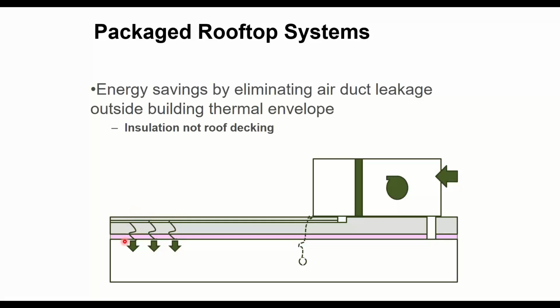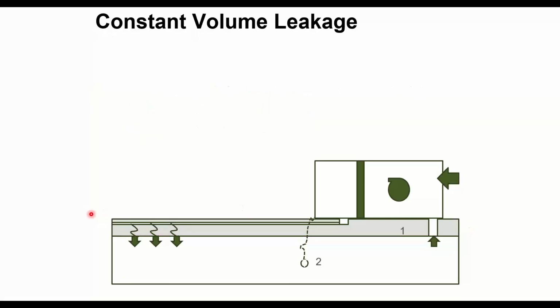But in regards to the air leakage, see if the little arrows pop up for me, right? All the air that's leaking out of my ducts in the ceiling cavity is actually leaking out of the building in most cases. If I have ductwork in the space and it leaks, it's like, oh, okay, you got leaky ductwork in your space. At least it still gets to the space. But when it leaks in ceiling cavities, walls, shafts, some of that might go back to the space. Some of it goes directly to the outdoors.